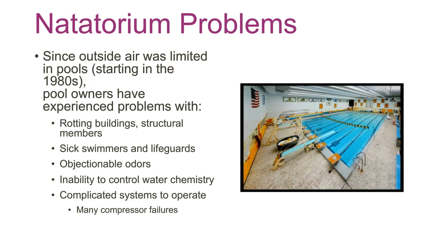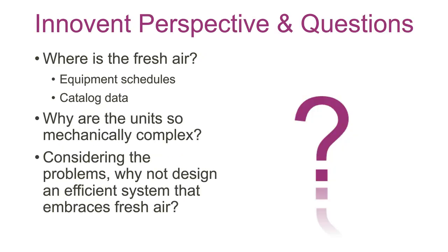And this is really, when we entered the market in the mid-90s, those were issues that were happening. And when we started looking at it, our perspective was, well, where's the fresh air in this application? If I looked at equipment schedules back then, oftentimes outside air wasn't even listed. If outside air was listed, the temperatures associated with the outside air and the humidity weren't listed. And the catalog data for a lot of the units that were being done didn't include outside air.